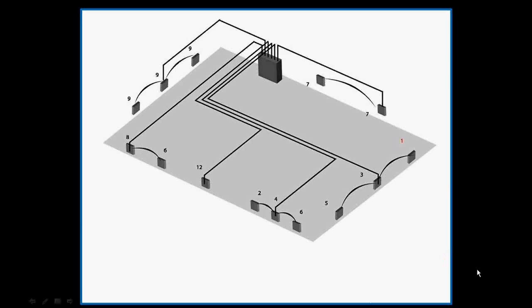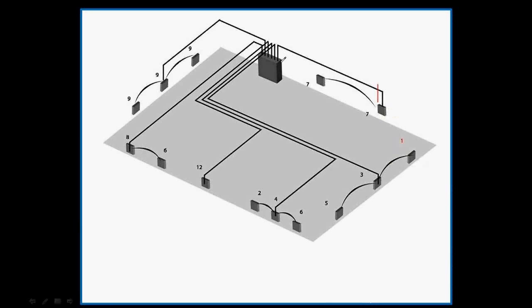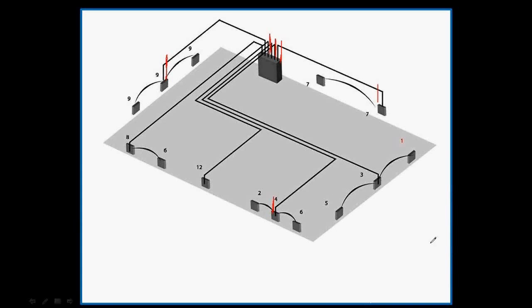When doing a conduit takeoff, you must include the length of the conduit risers. Now here are the conduit risers, which are the conduits that run up or down. Conduit risers are not depicted on a normal blueprint or drawing, but you must account for them. I will account for the conduit risers by over-rolling the Scalex. These are the risers right here.